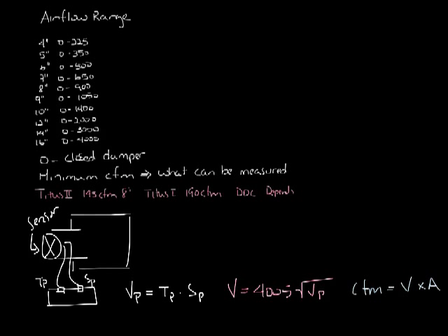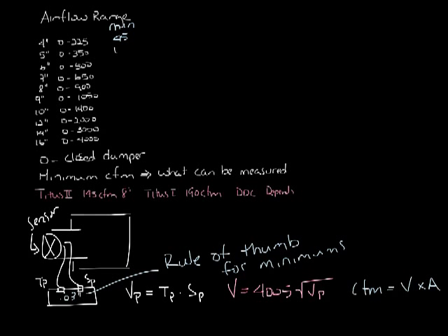If you remember, this is velocity equals 4005 times the square root of the velocity pressure, and then it can use that to calculate the CFM, which is velocity times area. So a good rule of thumb is that the pressure transducer in a controller needs about 0.03 inches of pressure differential.